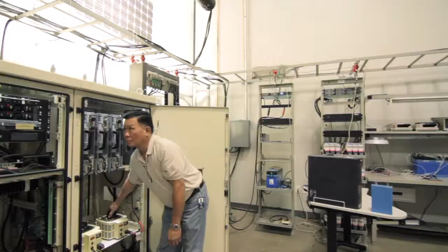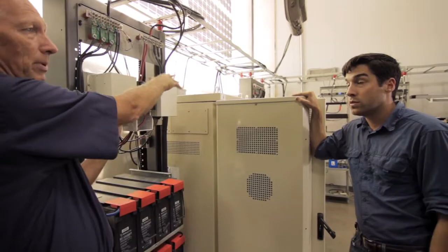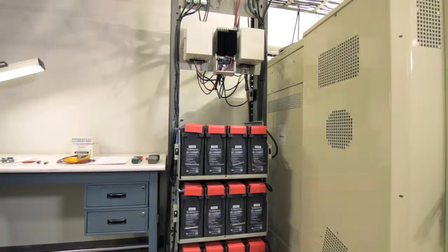Starting over here, I've got two big rheostat controllers so I can control the speed of the turbines. Over here on this bay, I have the controllers: these are the two turbine controllers, and this is the solar controller that's tied into my power plant. So all of this equipment, including this rack and that rack, connects to the same bus as the rectifiers do. The batteries are another load on it, just like the radios are down in that cabinet. All of that connects together, which is what we're trying to achieve here: an uninterruptible source of power.